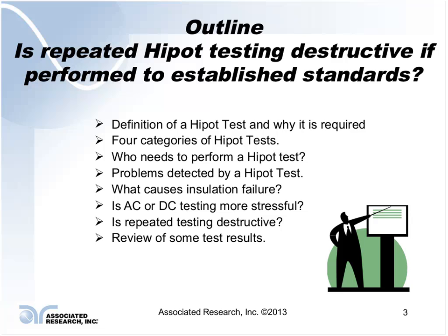where we've set it up and done some repeated testing on it and monitored leakage currents during the test time. We did not take these products to the point of destruction. So I don't know if I can actually answer the question, how many tests are too many, but we can give you a pretty good representation of what actually went on during the test itself.